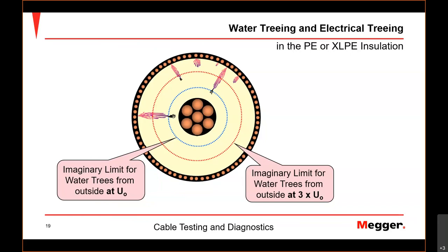If you see partial discharge, you already know you have to fix some problems. Then you might do a tan delta measurement just to make sure you don't have water treeing, if it is an aged cable. If it's a new cable, you might not need to do tan delta because a new cable cannot have water treeing. Then you might do a VLF test.